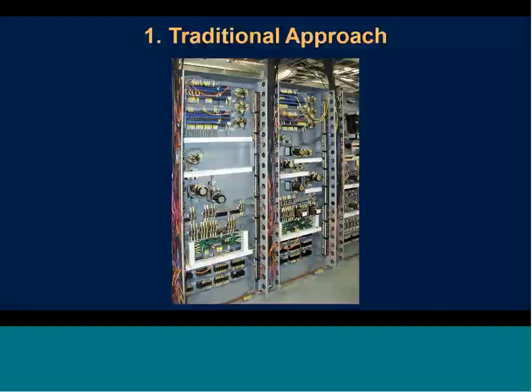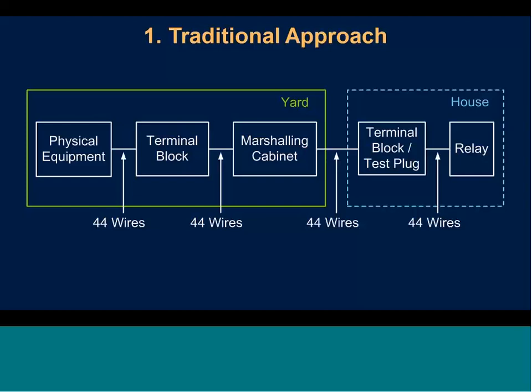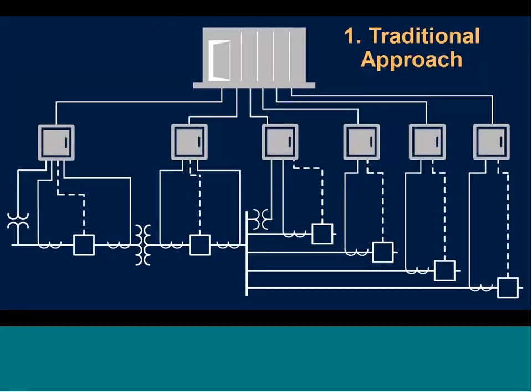So first, let's do a quick overview of what a traditional approach might look like. In an example system, we essentially wire everything from the equipment all the way to the relay. Along the way, we would generally put it into some kind of marshalling cabinet in the yard, and then have a trench where we send all that wire to the control house, where we wire it into a test block or a test switch, and then to the relay. So with that, in our example, we have 44 hard wires. From an architectural standpoint, it would look something like this, where we have all the connections, we bring them to a cabinet, and then run it all back to a centralized control house.